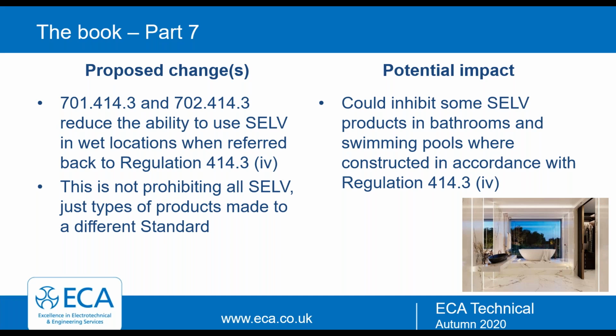701, while you're here, Luke - there's a new regulation being proposed about SELV in bathrooms. Is this prohibiting SELV? No, there was a lot of talk around that. This was actually about prohibiting the use of SELV in bathrooms, but it's not as strict as that. You just have to be careful what equipment you use for providing SELV within a bathroom. This is more to do with an issue with the product standard, which I believe is 62368, which some devices are manufactured to, and these wouldn't be able to limit a dangerous voltage going through under a single fault condition.